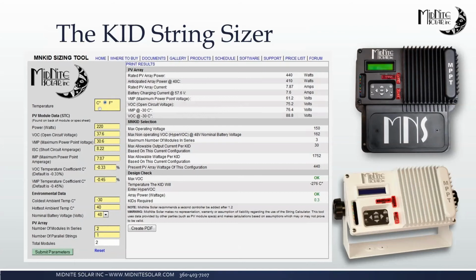You'll also notice that this number down here doesn't turn yellow or red until we go above 1.2. And the reason for that is because if you look at the data sheet or the nameplate on the back of a solar module, it's going to say like 220 watts. And then it's going to have this little term called STC, Sierra Tango Charlie. And STC stands for Standard Test Conditions, and that's in a lab at exactly 1,000 watts per meter squared. In the real world, we never have the blue enough sky. We never have the proper enough angle. Nothing really ever aligns to get anywhere near that 1,000 watts per meter squared.